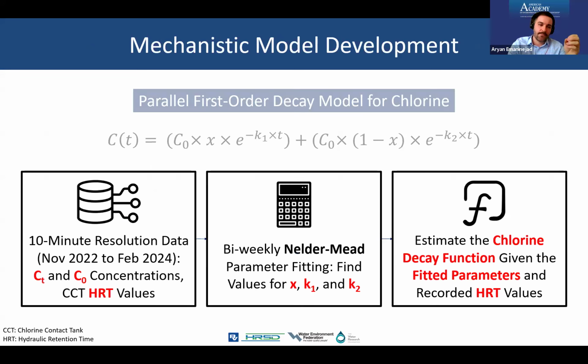Using that mechanistic model and the data we had - high resolution data from November 2022 to February 2024 at 10-minute resolution, with measurements for chlorine concentration at time t, initial chlorine concentration, and HRT values - we first used a parameter fitting approach called Nelder-Mead to find the values for x, the fraction that gets decayed, and our equation constants.